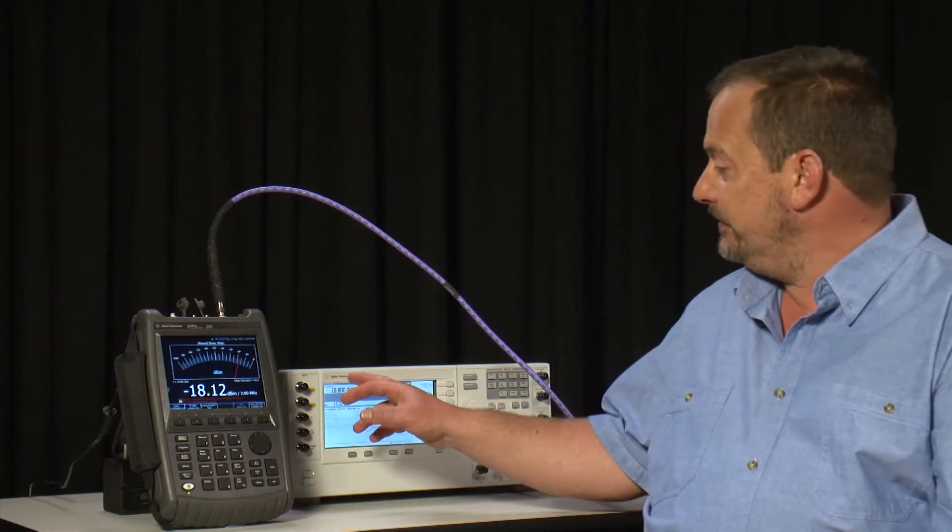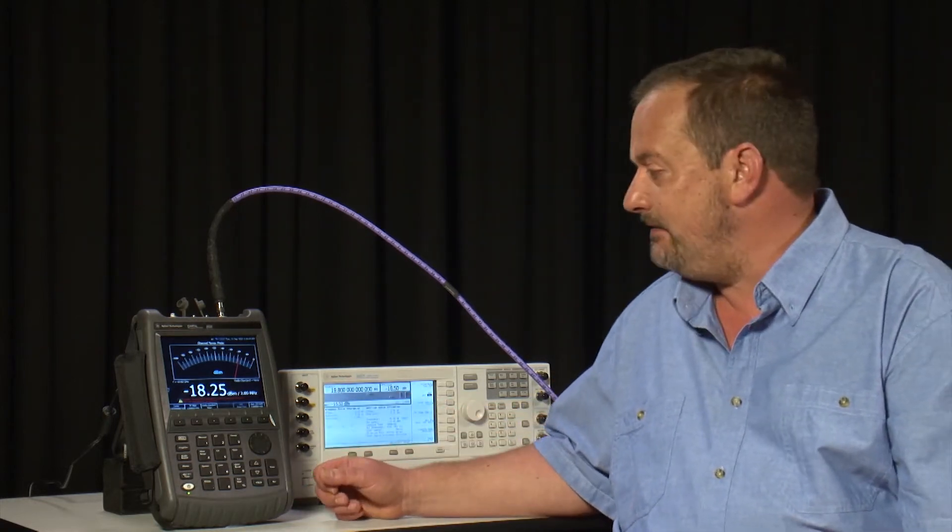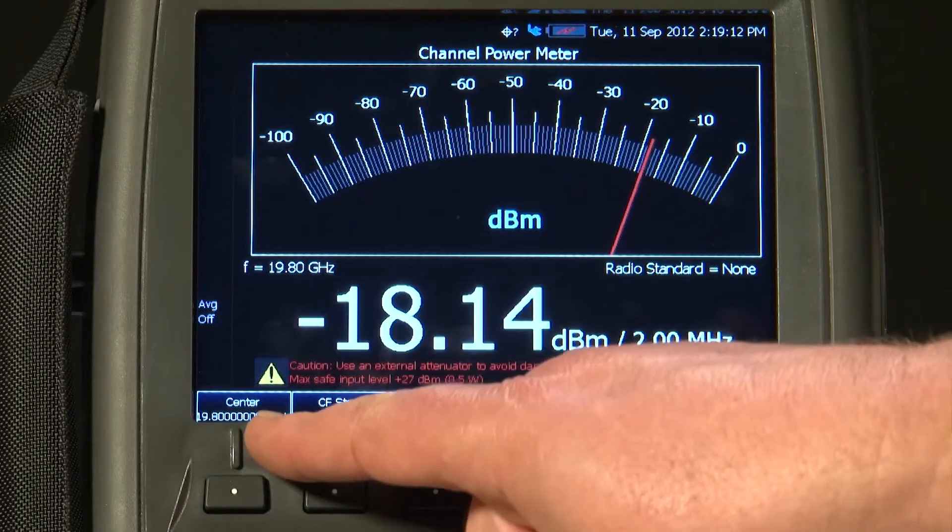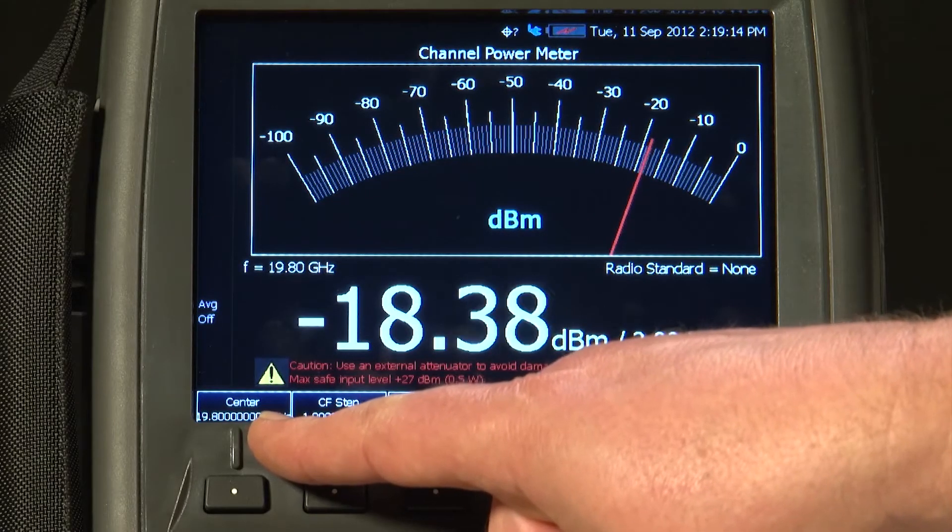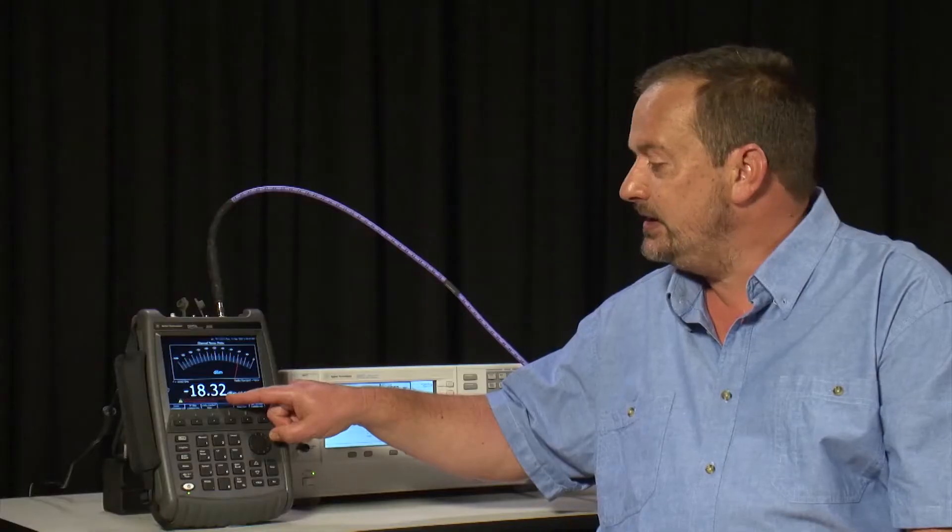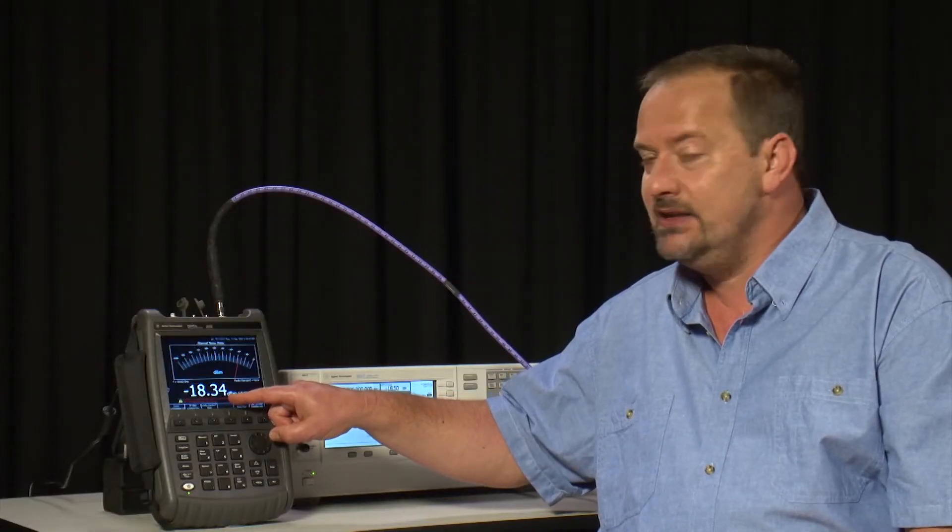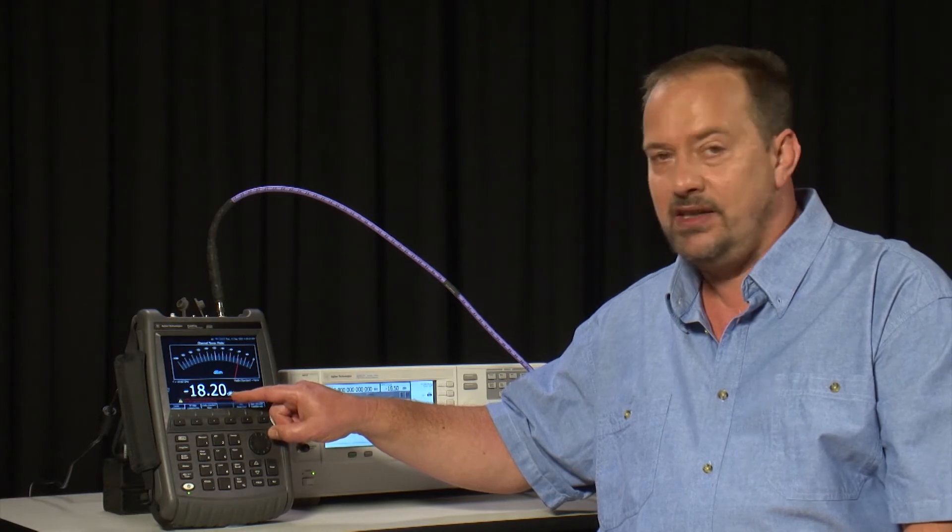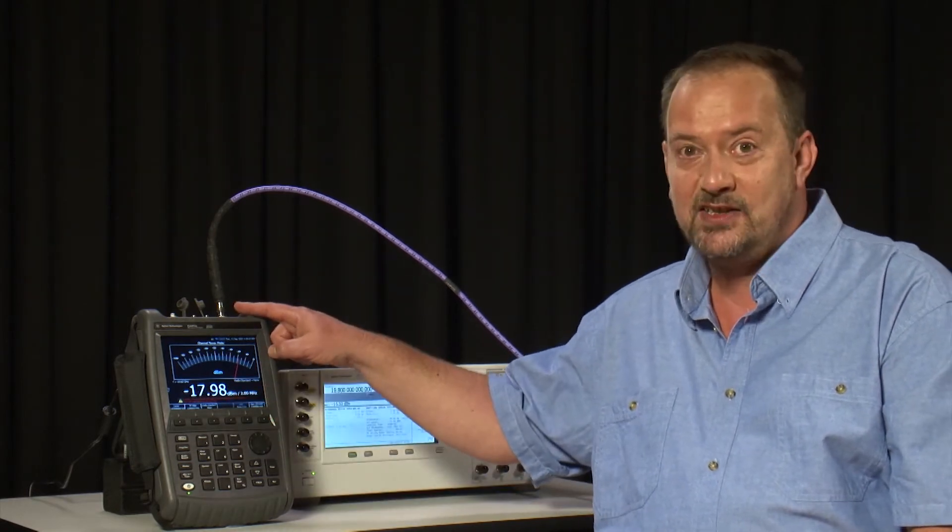So here we are still generating a 19.8 GHz spread spectrum carrier, and we have set the center frequency to 19.8 GHz. There is a red warning on the screen here, which is just a little reminder that if you are connecting directly to a transmitter, you really ought to think about also inserting an external attenuator.